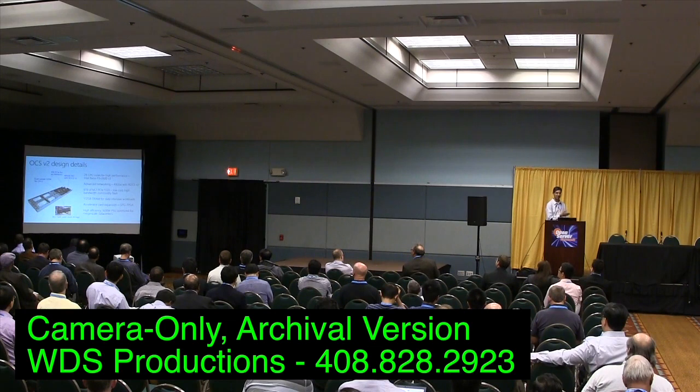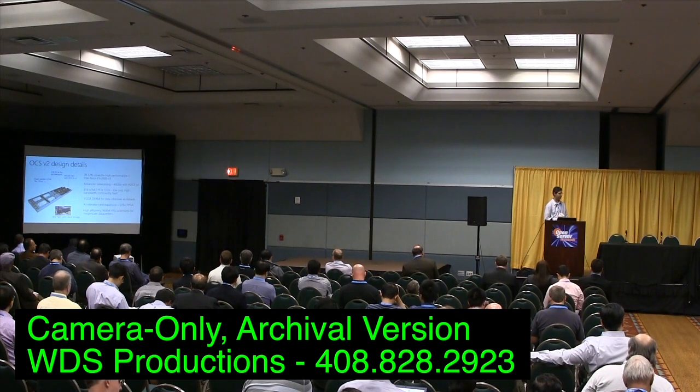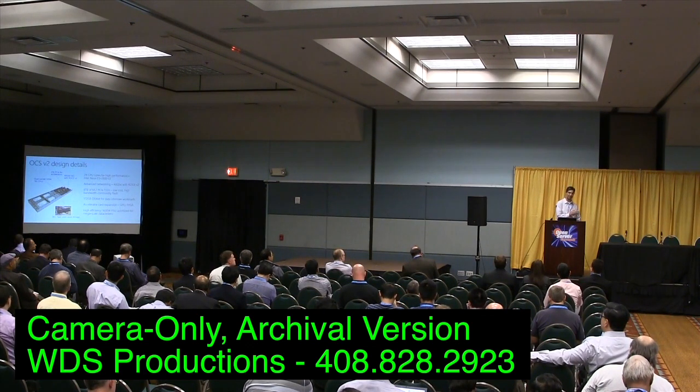And finally, for the data center integration, there is a 1600 watt power supply that is not only highly efficient, but it also is designed for load transfer considerations in the data center. There's a 20 millisecond hold up time in the power supply, so that when the power goes out, the utility, the load is still going to be seamless while it transitions over.